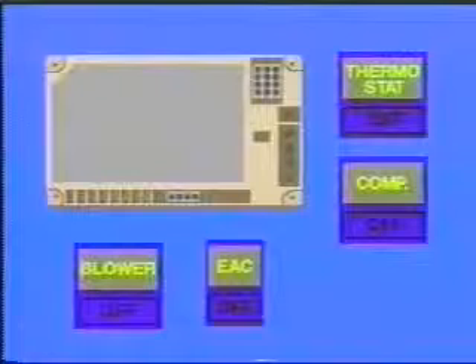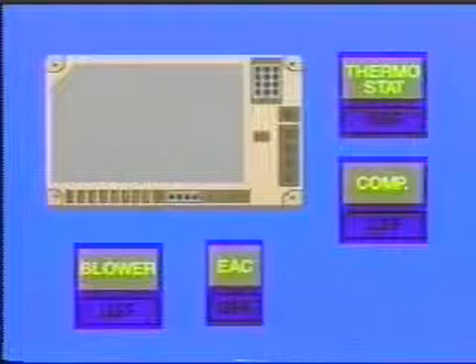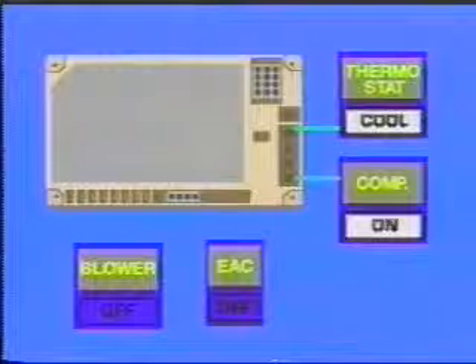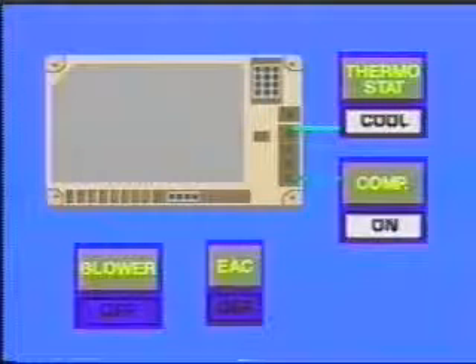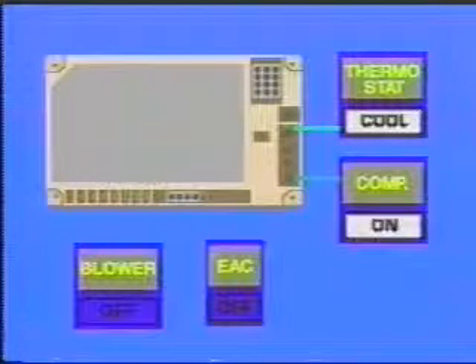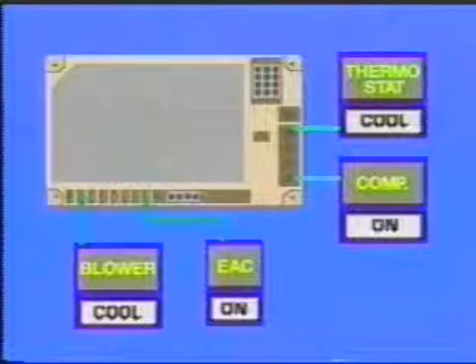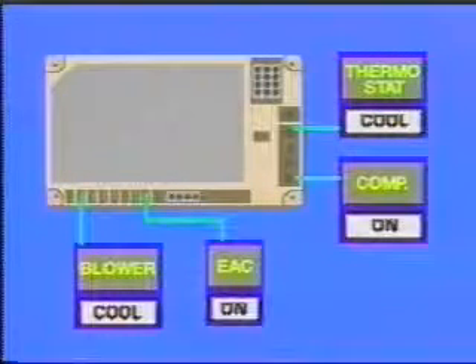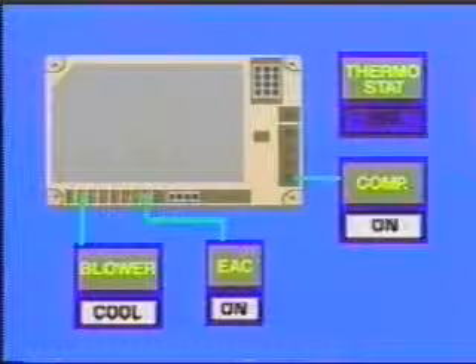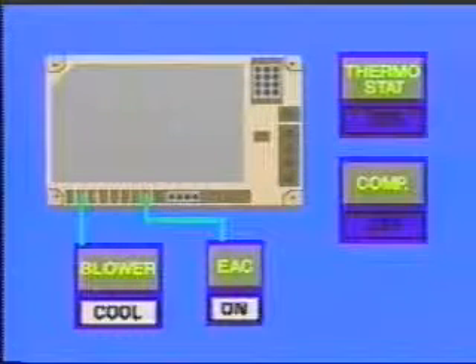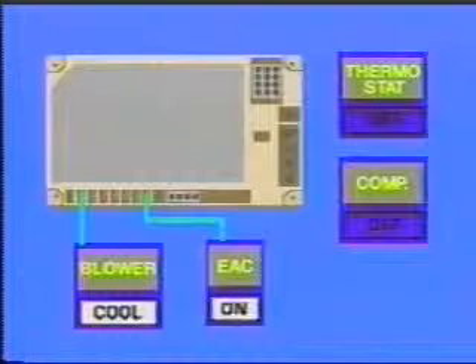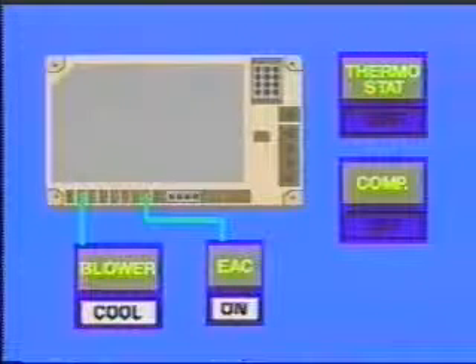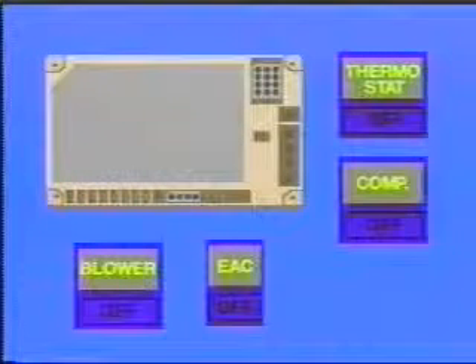The cooling sequence is much like that of a conventional system. The difference lies in the cool fan speed delay off. When the thermostat calls for cooling, the compressor contactor is immediately energized. If an air cleaner is used, it too is energized along with the cooling speed of the blower. After the thermostat is satisfied, the compressor contactor is de-energized and the optional cooling delay to fan off period begins. At the end of the timer period, the blower and air cleaner circuits are de-energized.